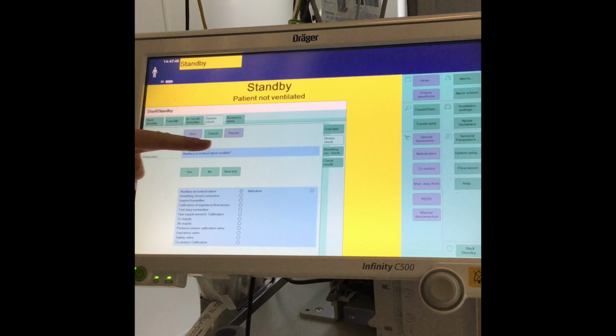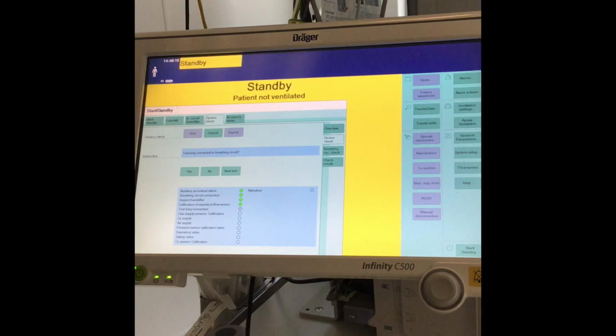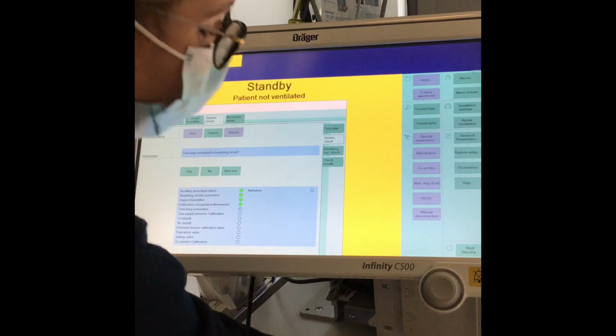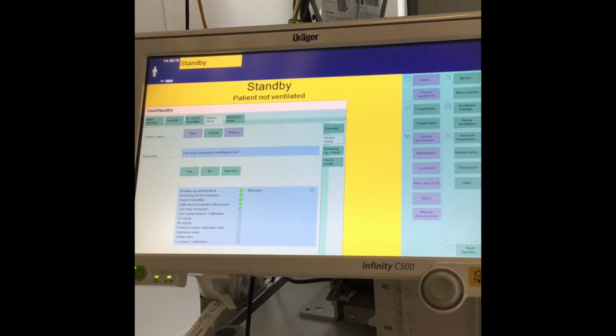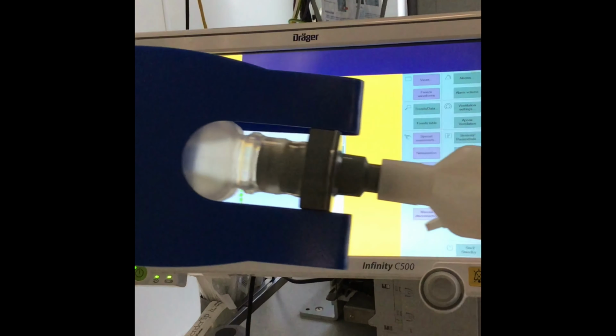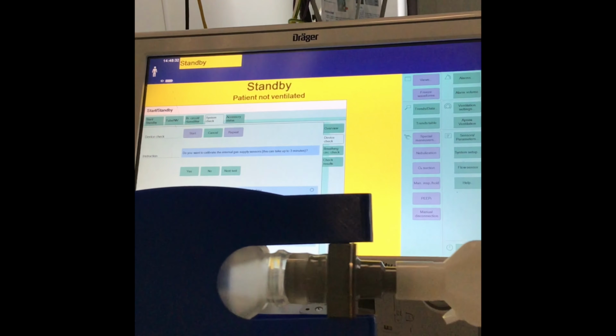All of the instructions come up here, so you can hear an audible alarm, so you'll just hit yes. The breathing circuit connected correctly, as far as we're aware, it looks like it's connected correctly, so we're going to hit yes. The humidifier connected correctly or not in use. Everything, as I say, looks as though it should be connected in the right place, so we'll hit yes. And it's going to say to connect the test lung. Test lung to the patient end of the circuit. I'm just going to hit yes once it's connected.